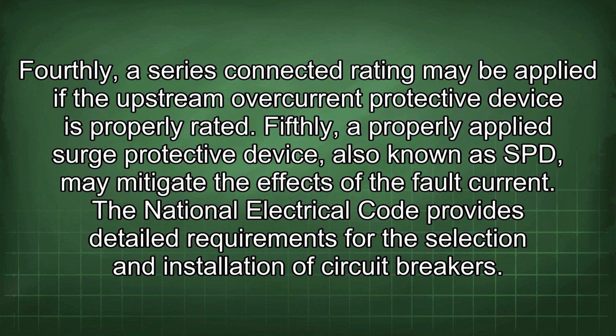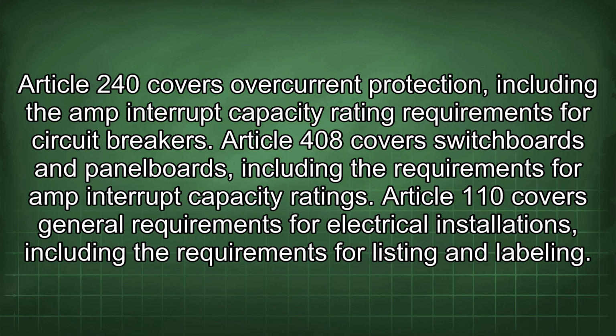Fourthly, a series-connected rating may be applied if the upstream overcurrent protective device is properly rated. Fifthly, a properly applied surge protective device, also known as SPD, may mitigate the effects of the fault current. The National Electrical Code provides detailed requirements for the selection and installation of circuit breakers. Article 240 covers overcurrent protection, including the amp interrupt capacity rating requirements for circuit breakers.